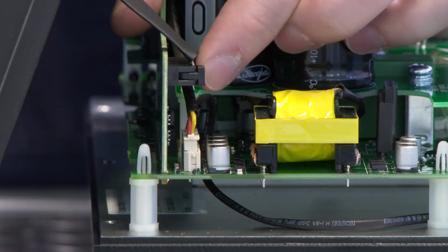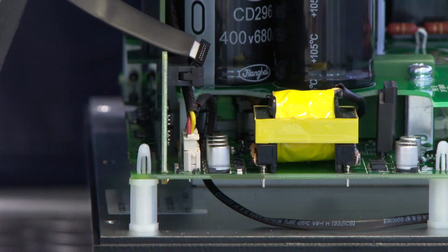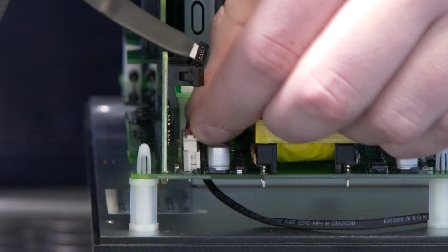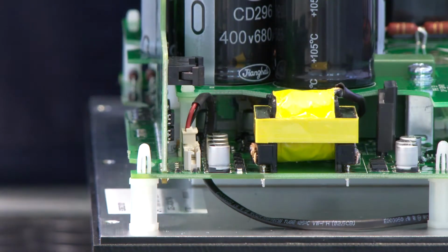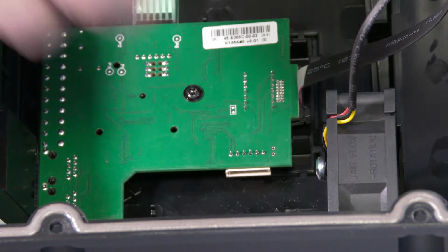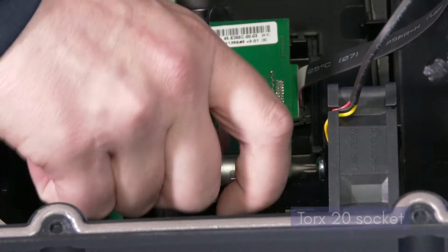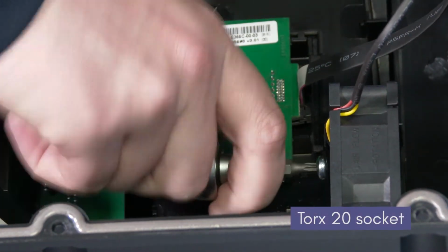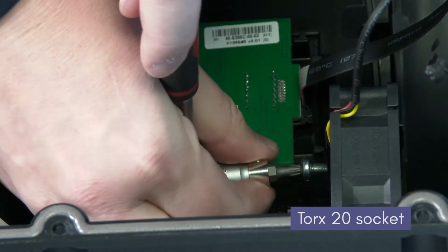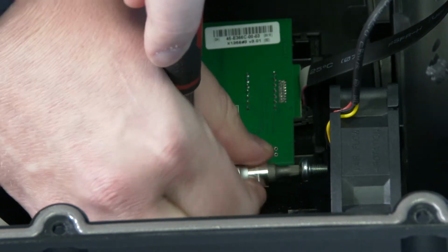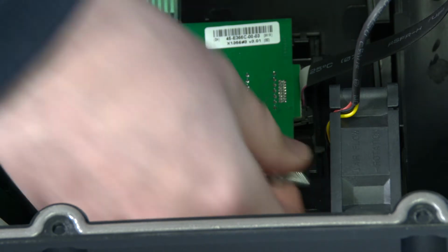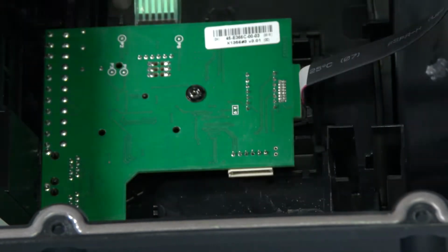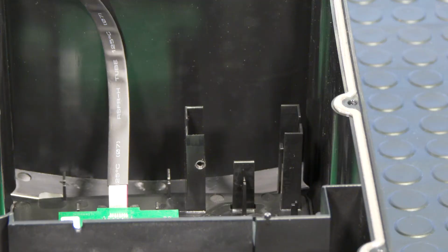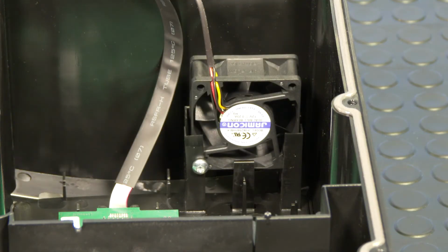Disconnect the ribbon cable from the power board by pushing the 2 tabs back and pulling the cable away. Disconnect the fan from the fan connector. To remove the internal cooling fan from the fan bracket, use a Torx 20 socket to remove the screw holding the fan in place, and unclip and lift the fan away. Replace the internal cooling fan using the parts supplied in the Preventive maintenance kit.